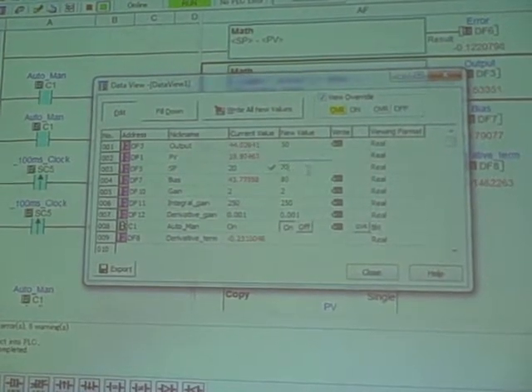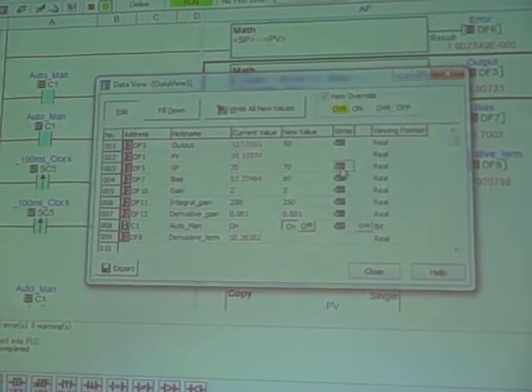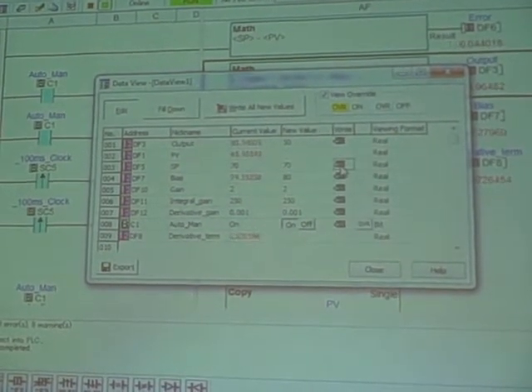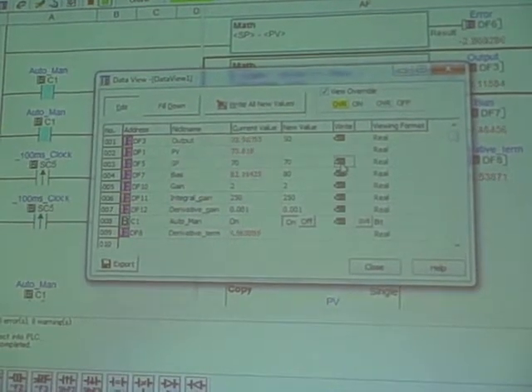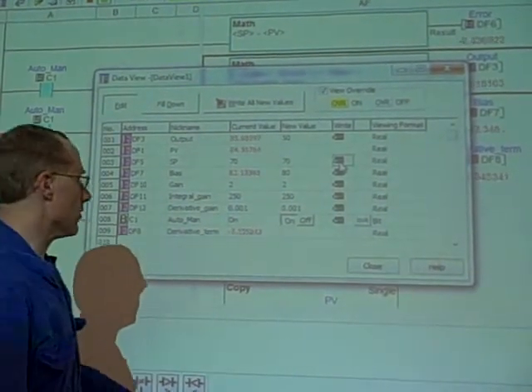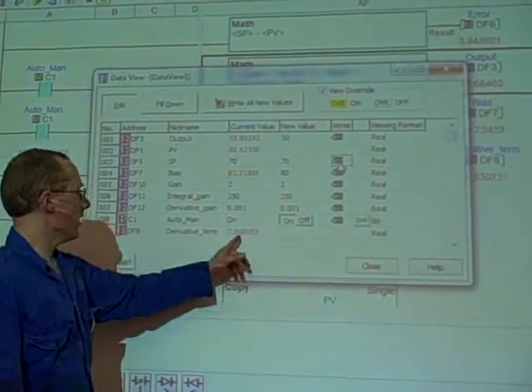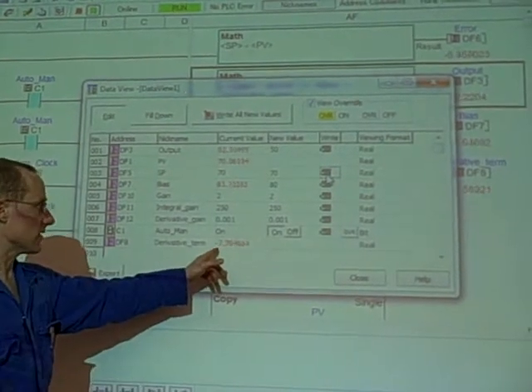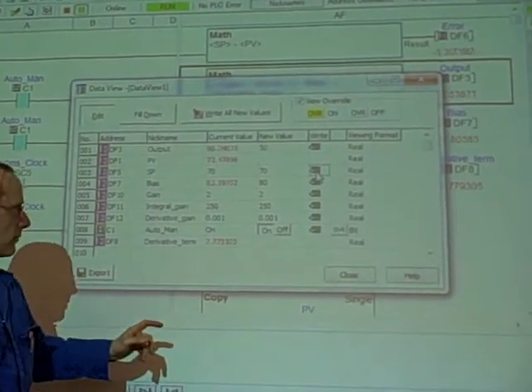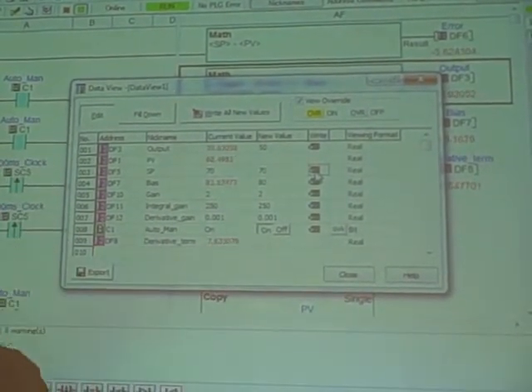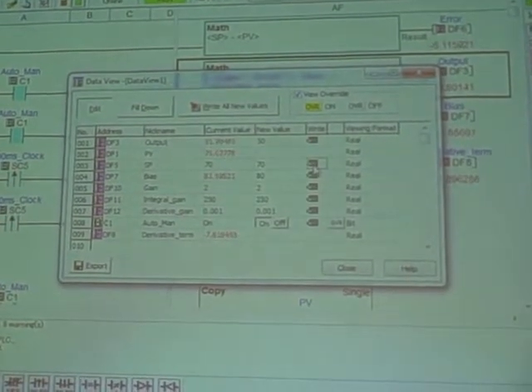Let's try this. Let's go back to the setpoint of 70. You can hear the oscillation. It's even getting worse. Our derivative is reacting excessively to the rates of change it sees in the motor. We need to slow that down by putting in a tamer derivative term.